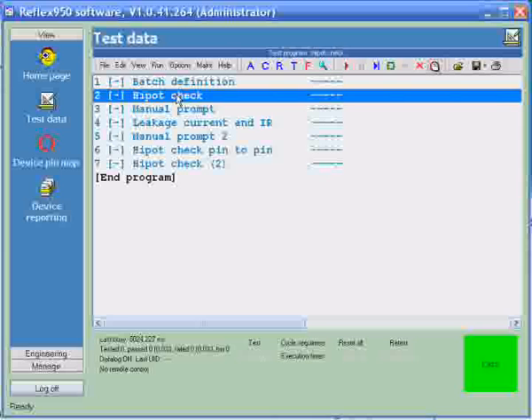At the bottom we have a list of pins that for this test step will be connected high. In the case of the hipot test, high means connected to the application test voltage. We also have a list of pins which will be connected low, meaning the detection mechanism for measuring any hipot current flowing. And we have the possibility to specify pins that will be grounded, taking no part in the test.